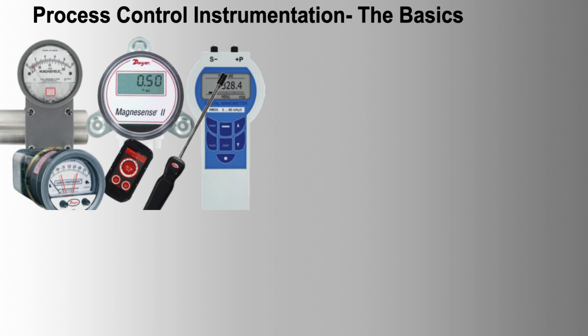5. Installation location. Proper placement is essential to avoid issues such as vibration, high temperatures, and accessibility for maintenance. 6. Hazardous area certification. Ensure the instruments are certified for use in potentially explosive environments, e.g. ATEX, IECEx. 7. Redundancy and reliability. Implement redundancy in critical measurement points to ensure reliability and safety.